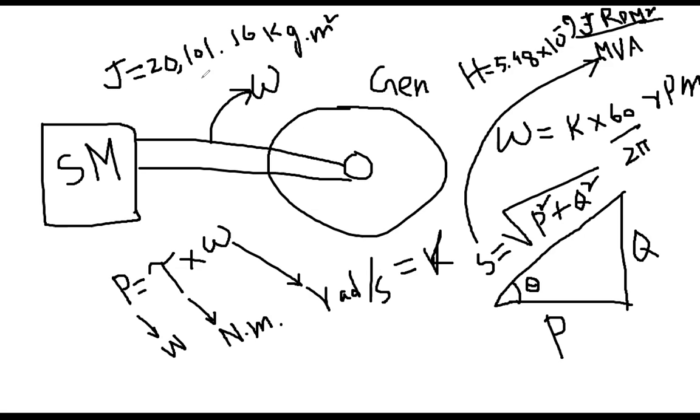Okay, Manoj, did you try? Yes, Dr. Ali. Is my answer correct or have I deviated? So what was your RPM? 1425, right? That is right. Yes, Dr. Ali. And then the S value here is 89.44 MVA. Yes, same. Okay, great. So everybody, please follow and try with me. This should be 89.44 MVA.